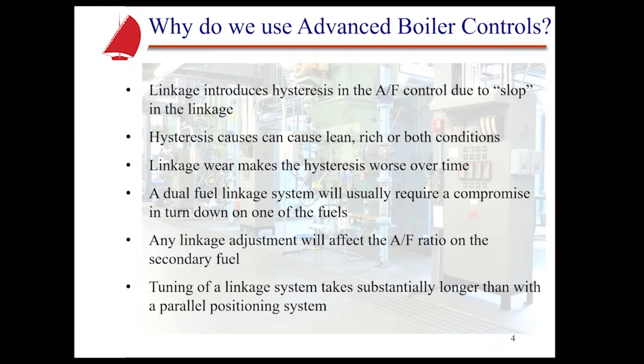The whole purpose for air-fuel ratio control is to be as close to perfect as possible. And linkage, quite honestly, wears over time. And when that wears, the slop or hysteresis gets worse over time. So we don't have that perfect combustion that we really desire. And every burner has a perfect combustion point at any point across low fire to high fire.